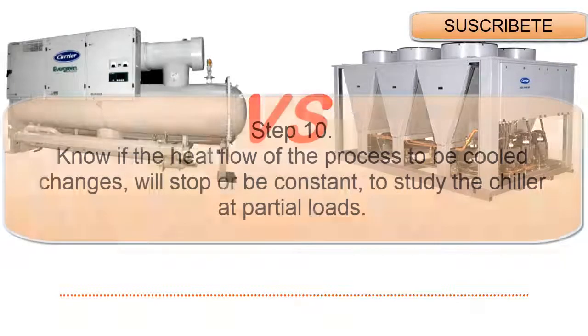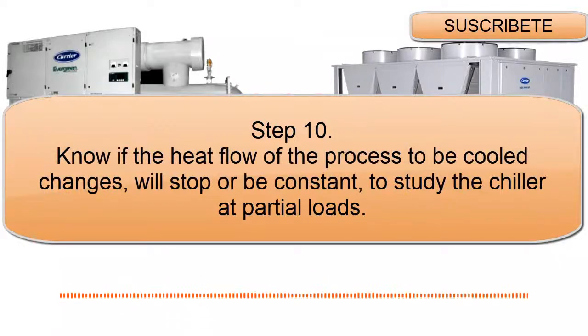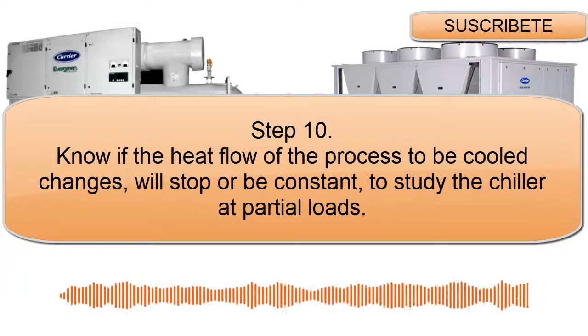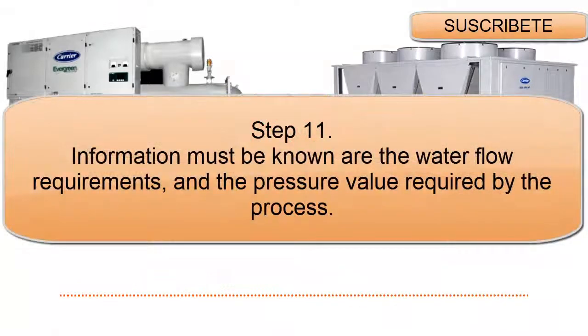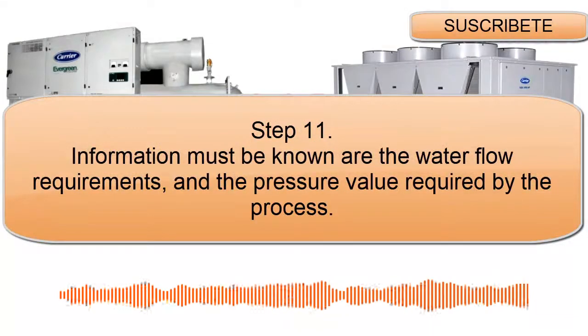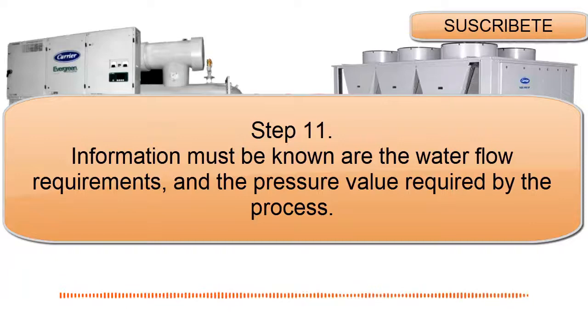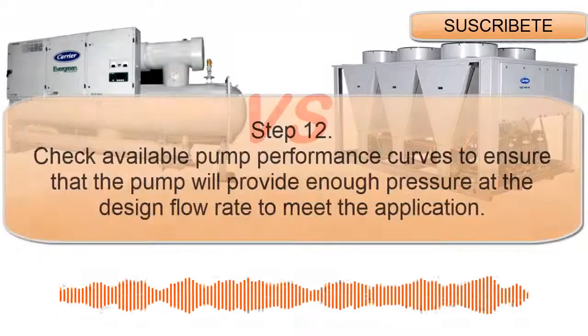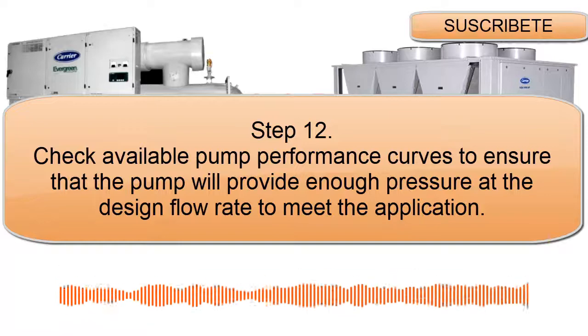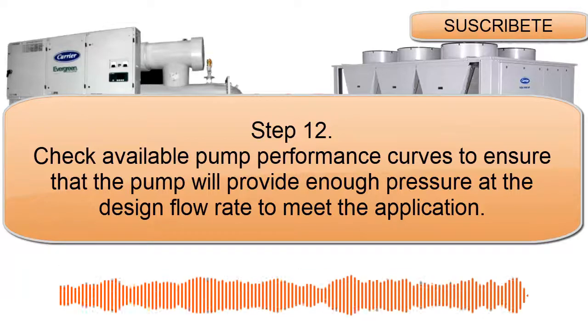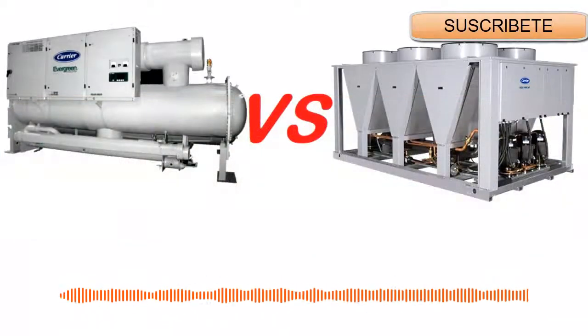Step 10: Know if the heat flow of the process to be cooled changes, will stop, or be constant, to study the chiller at partial loads. Step 11: The water flow requirements and the pressure value required by the process must be known. Step 12: Check available pump performance curves to ensure that the pump will provide enough pressure at the design flow rate to meet the application.